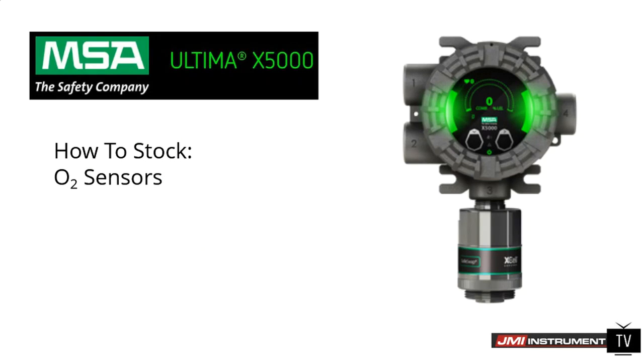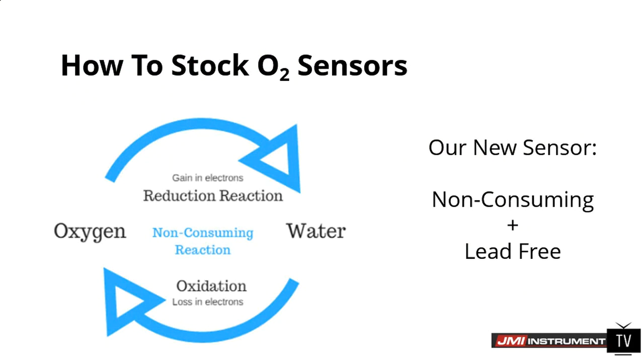So when we talk about how to stock O2 sensors, we've got to talk about how O2 sensors actually work. In the past, O2 sensors were typically good for a 1-year warranty, maybe an 18-month to 24-month lifespan. The reason why you couldn't stock them is because electrochemical sensors by nature are detecting gas whether they're plugged in or not. And now in our new oxygen sensor, we can actually not have that sensor deplete when it's sitting on the shelf because it's not active and it's not consuming itself.